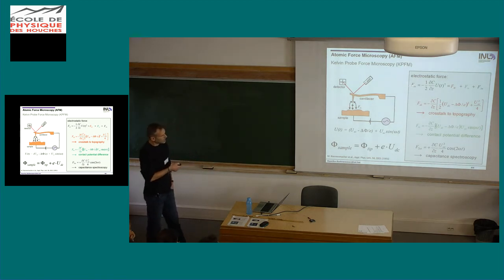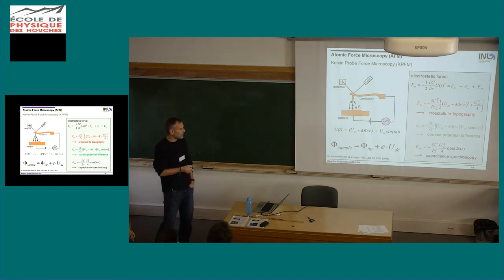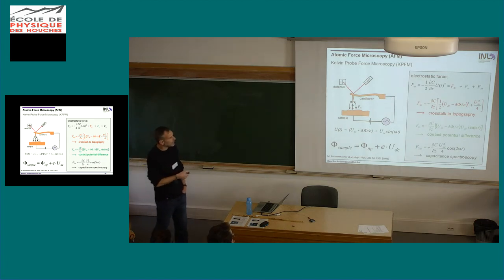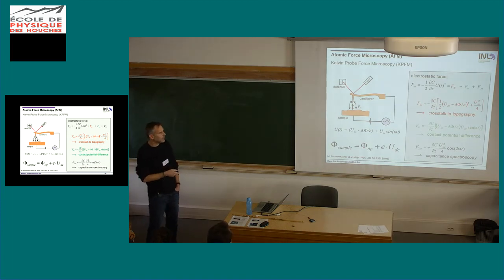And then the electrostatic force between tip and sample is written here. We just take the voltage squared. So if we plug this in, we get three terms. One is a DC term. One is a term that is the force at the frequency of the AC bias that we apply. And one is a force at double that frequency. This is just by taking out the mathematics, the square. So the DC part actually contributes to the topography. So this is an addition to the topography. And then what's important for Kelvin probe force microscopy is this force at the frequency of the AC bias.